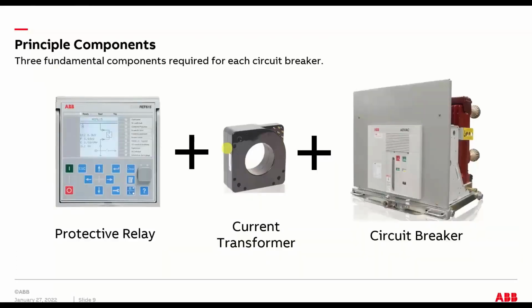Fundamental, the basic parts we already discussed are the relay itself. This is an example of an ABB numerical relay, current transformer, and circuit breaker. So you need at least these three pieces to make a complete circuit breaker system. And this circuit breaker is a vacuum breaker used for medium voltage switchgear, but it could be a whole slew of different breaker technologies, sizes and configurations. It's just a medium voltage metal clad switchgear example.